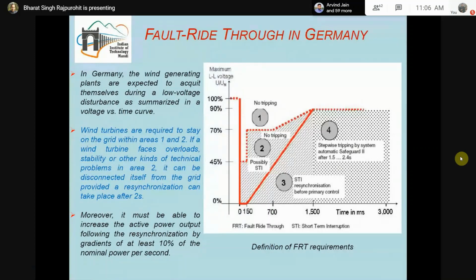solid line says that if the voltage is reduced to 0 during 0 to 150 milliseconds, the wind farm should remain connected to the grid. So above this red line, the wind farm should remain connected to the grid and there should be no tripping, even if the voltage is 0 at the grid for 0 to 150 milliseconds.